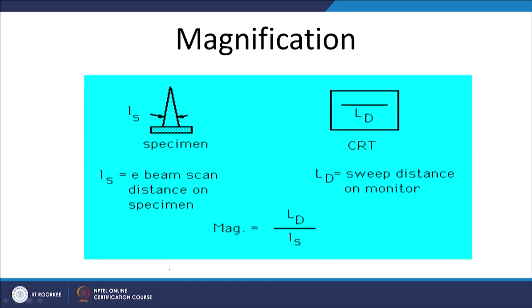In terms of magnification, if Iₛ is the electron beam scan distance on the specimen (typically kept at 8 mm) and LD is the sweep distance on the monitor CRT, then magnification is defined as LD divided by Iₛ — the sweep distance divided by the electron beam scan distance.